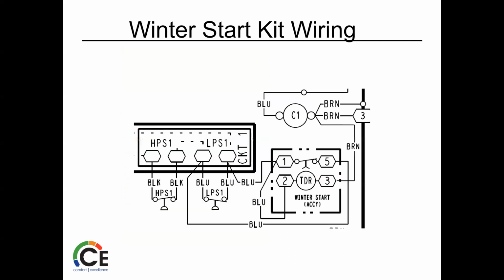So here, we'll skip that and go to here. Again, you can see down at the bottom, we're not disconnecting the low pressure switch. We're leaving that hooked up, and that's the biggest mistake that we get phone calls for. Guys are cutting those wires or taking them off. It happens, right? So we're literally just adding this winter start control to that circuit.